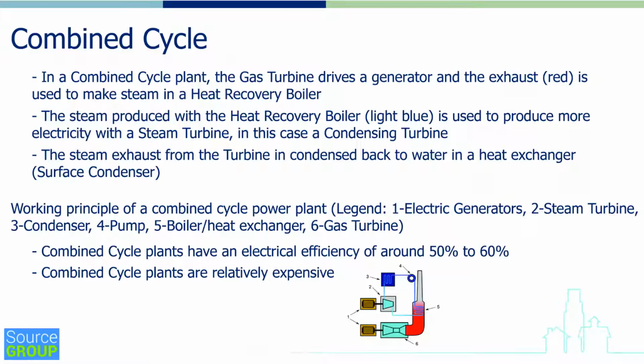Combined cycle. In a combined cycle plant, the gas turbine drives a generator, and the exhaust, indicated in red in the diagram, is used to make steam in a heat recovery boiler. The steam from the heat recovery boiler, which is shown in light blue, is then used to make more electricity with the steam turbine. In this case, it's a condensing turbine. The steam exhaust from the turbine is condensed back to water in a heat exchanger, generally called a surface condenser. Combined cycle plants have an electrical efficiency of around 50 to 60%. They are also relatively expensive.